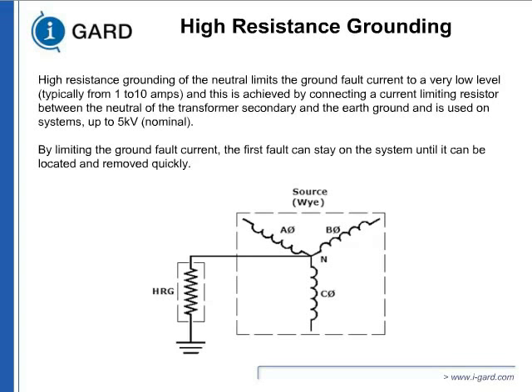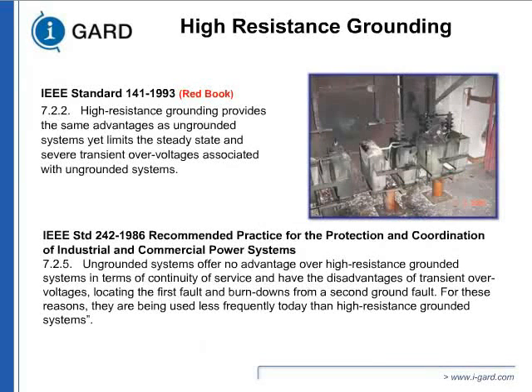This is a quote from the IEEE Red Book, and if you look at the date, it is 1993, so very old technology. IEEE standards do not move that fast. In 1960, when we introduced this technology in our sites, I say we, I was not the principal designer, I was a user. The Red Book, which was the primary document engineers used for design, first time mentioned that high-resistor grounding has the same advantage as an ungrounded system because you can run right through the first fault. It gives you other advantages. It limits transient overvoltage because now the electricity has a reference.